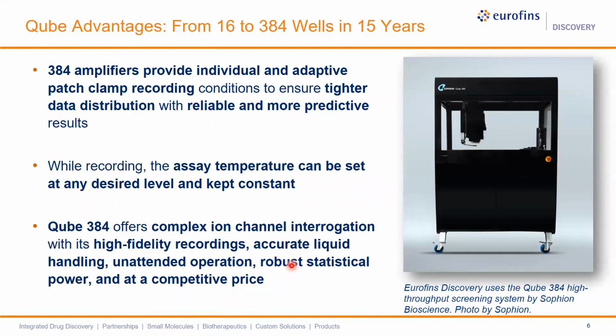And the other thing is that once you start the assay, for example, at 37 degrees Celsius, it's locked in, and until the assay is done, nobody can change the assay temperature. This is a good safety mechanism, and a mechanism I like in the Qube.